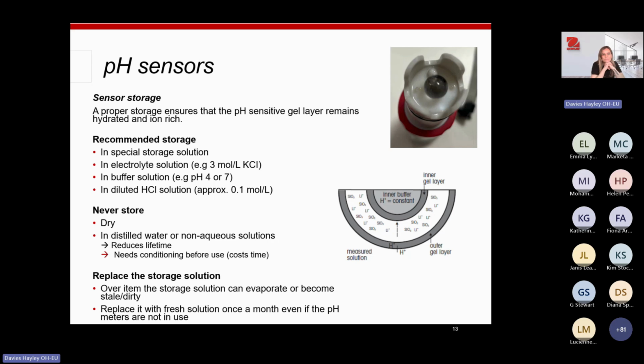So how to look after your pH sensors. Sensor storage, proper storage, make sure that the pH sensitive gel layer remains hydrated and ion rich. So this is the glass membrane or the tip or the bulb. Either description is fine. And inside that is that lovely gel layer, and it needs to be kept hydrated. It needs to be kept ion rich, and to do that, you should keep it in a special storage solution. So you can buy very expensive special storage solutions on the internet from your educational supplier.